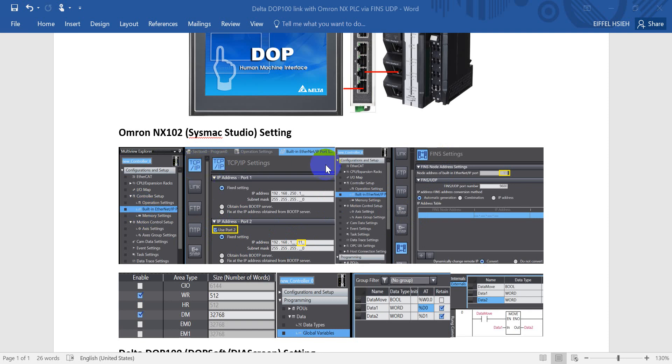After config the IP address, then we will go to the FINS setting. So you will see the node address actually will follow the IP address here. And FINS TCP UDP port default is 9600.